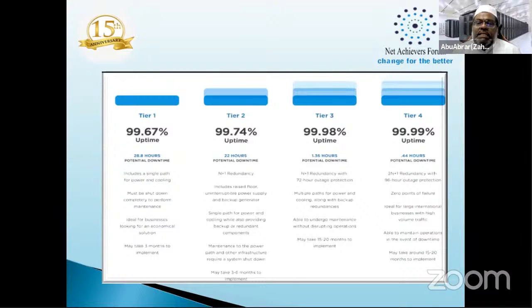It means it has N+1 with 72-hour outage protection, 72 hours total, with multiple paths of power and cooling along with backup redundancy. For example, you have 2 power paths. For multiple, it can be 2 or 3. Normally it is 2 because all of them are expensive. So you have 2 pathways of power from the main. The main also has a generator. Okay, one generator, applied for both UPS systems. Again, there is a bottleneck.